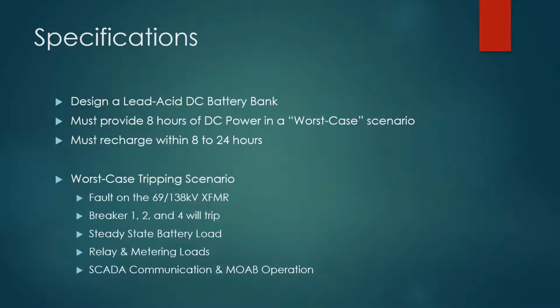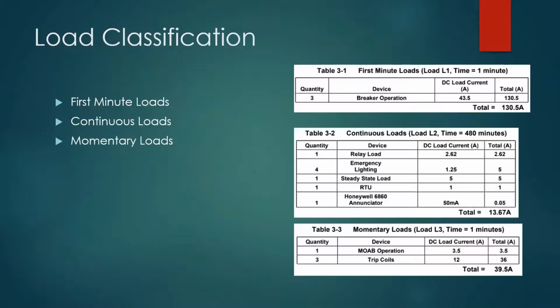The battery needs to be able to hold a steady state battery load, so it can't be drained to zero, otherwise that'll damage the battery. It must also be able to provide power to our relay and metering loads, as well as SCADA communication and operation of the motor-operated air break switch.